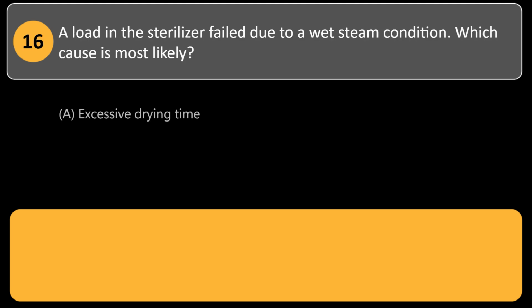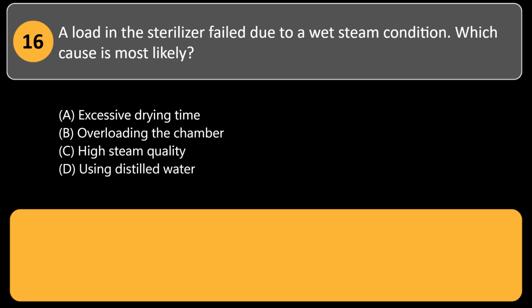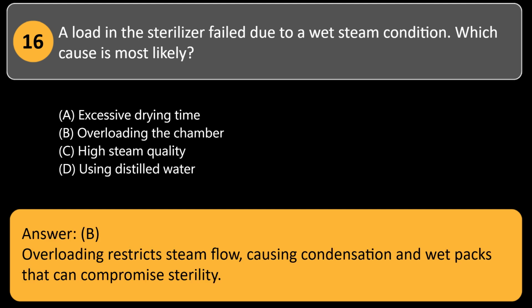A load in the sterilizer failed due to a wet steam condition. Which cause is most likely? A. Excessive drying time. B. Overloading the chamber. C. High steam quality. D. Using distilled water. Answer: B. Overloading restricts steam flow, causing condensation and wet packs that can compromise sterility.